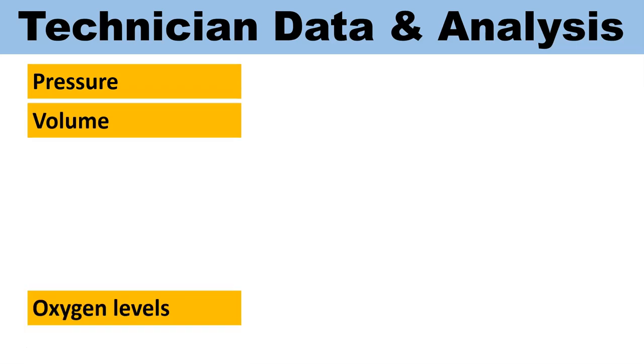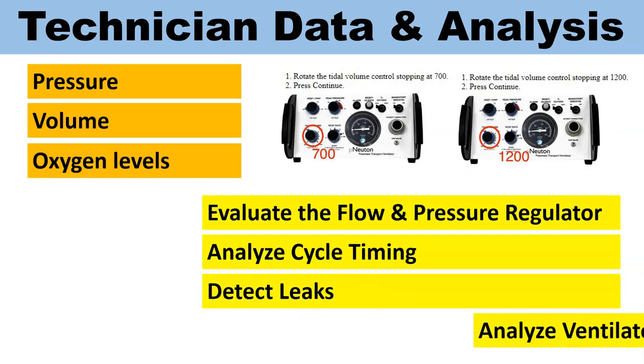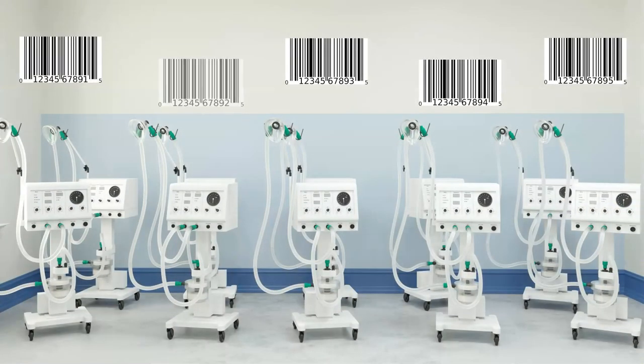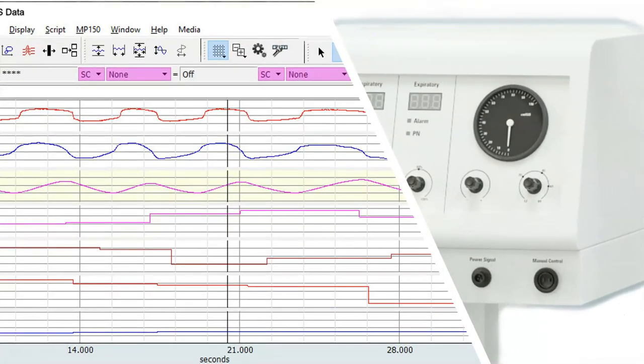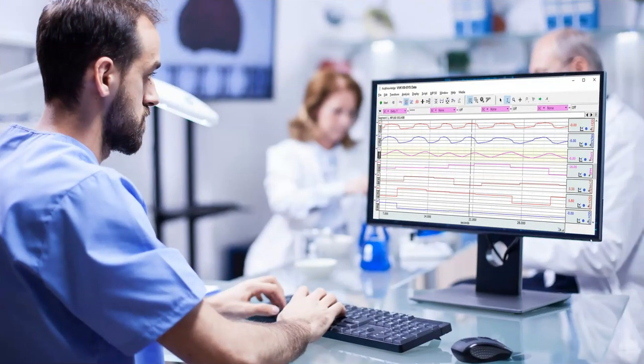Biopac's automated technician views prompt and guide technicians throughout the process to ensure maximum throughput and efficiency. Ventilators are tracked throughout the process using barcode scanners. Calibration and test data are matched to each specific ventilator. The raw test and summarized results are passed to teams for further analysis.